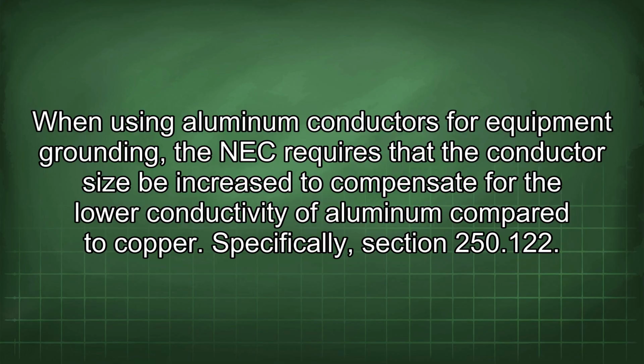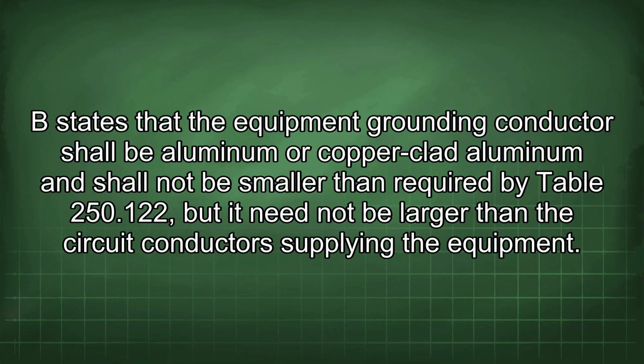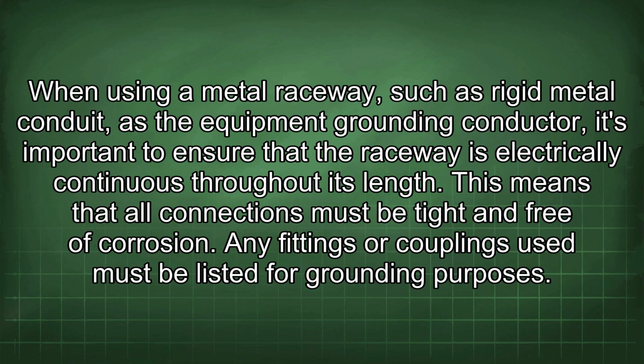Specifically, Section 250.122(B) states that the equipment grounding conductor shall be aluminum or copper-clad aluminum and shall not be smaller than required by Table 250.122, but it need not be larger than the circuit conductors supplying the equipment. When using a metal raceway, such as rigid metal conduit, as the equipment grounding conductor, it's important to ensure that the raceway is electrically continuous throughout its length. This means that all connections must be tight and free of corrosion.